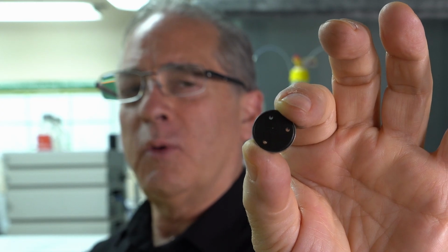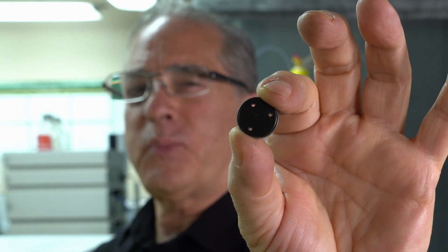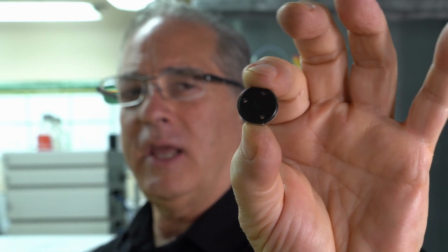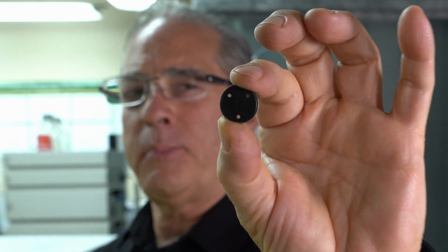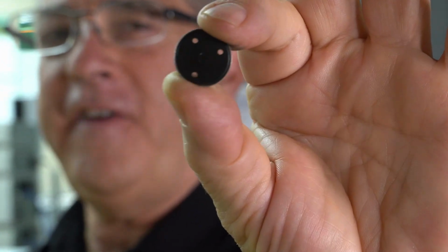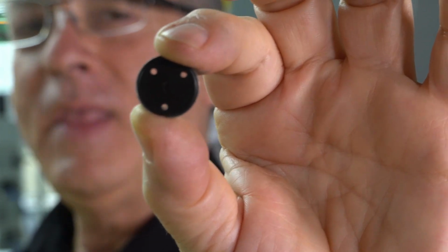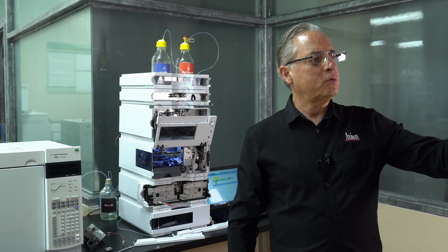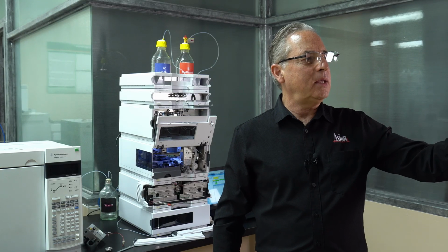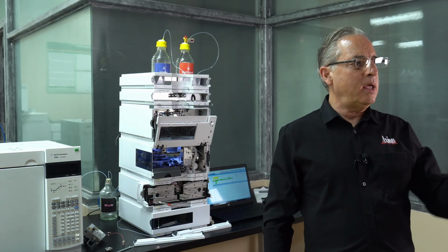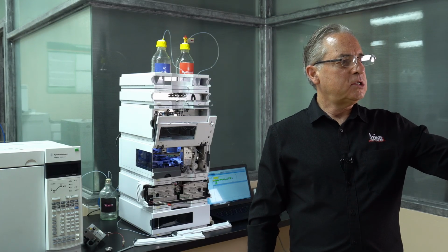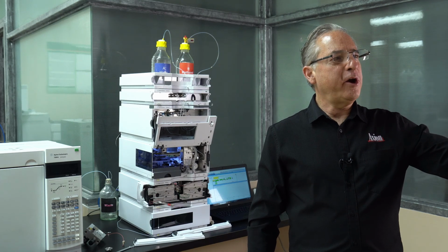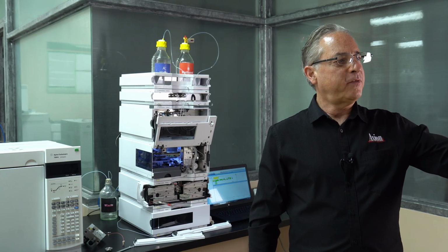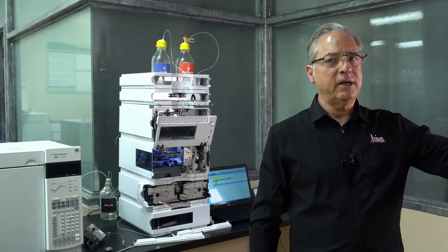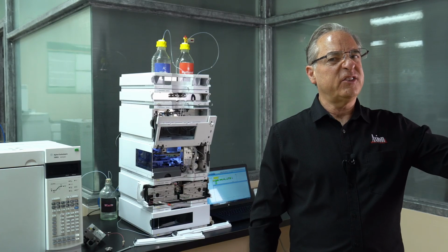So what could go wrong with this thing? Well, over time, this is pressed against a piece of ceramic, and it rotates 1/6 of a turn every single time, and they're pressed together really tightly. Eventually, the face of that is going to wear out. And when it wears out, there's one and only one thing that happens, and that is you lose area and height reproducibility. So when you have area and height reproducibility problems, the first thing we say is, let's just change that rotor seal. There's really nothing much else that causes that.